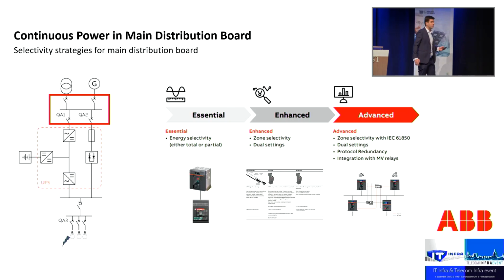So first, before starting on the selectivity between the UPSs and the breakers, which is, by the way, a more challenging task, let me share with you some strategies for the selectivity in the main distribution boards between the breakers typically, or also the fuses, but I would say, especially in the Benelux region, the breakers are the devices which are typically used. So the typical strategy for the selectivity is that I select the components based on the let-through energy, right? And so, based on the component selection, I have the selectivity between the downstream and upstream device. But sometimes I cannot do this, for many reasons. Maybe I need to install all air circuit breakers, all the breakers of the same size, in the main switchgear, so I cannot realize selectivity based on the selection of the device.